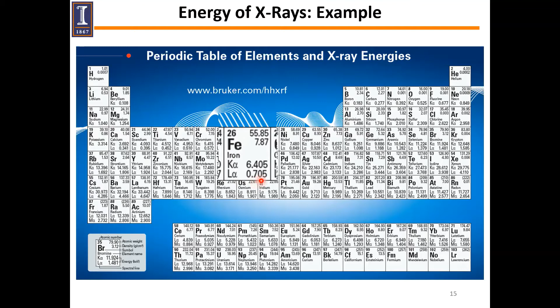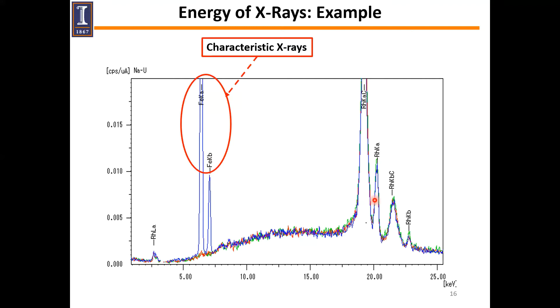Okay. If we see the spectrum for that sample, we can easily see this is the iron K alpha, and this is the iron K beta. These are the characteristics of this X-ray. One thing you can note is that the intensity is different, and I will come to how we understand the intensity difference and how we get quantitative results from this intensity. Besides the characteristic X-ray, you may also see other peaks here. These peaks actually come from the source, since we use a rhodium X-ray source, and these are artifacts. You will see this kind of artifact in an XRF spectrum, and I will explain each of these in a later section of my talk.